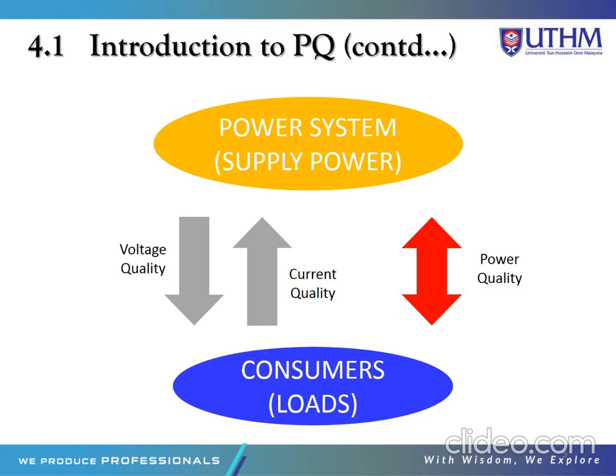This is the relationship between the power system, the supply power, and the consumer at the loads for PQ. We can see here, for voltage, voltage quality is affected by the supply power. Current quality is an effect from the consumer to the supply power. And for power quality, the effect is from both sides, from the supply and also from the consumer.